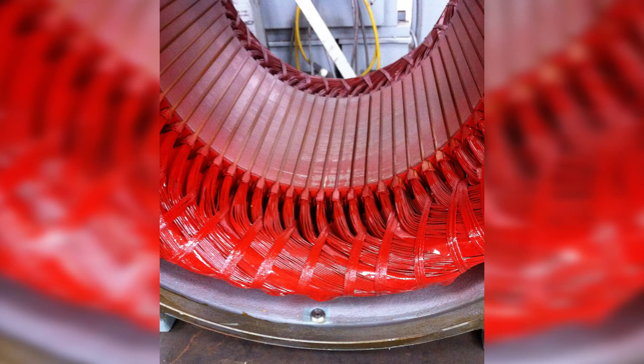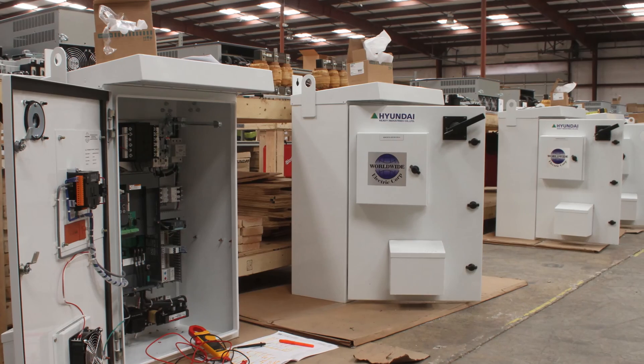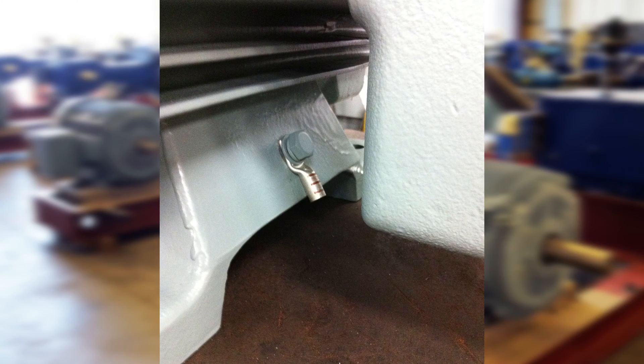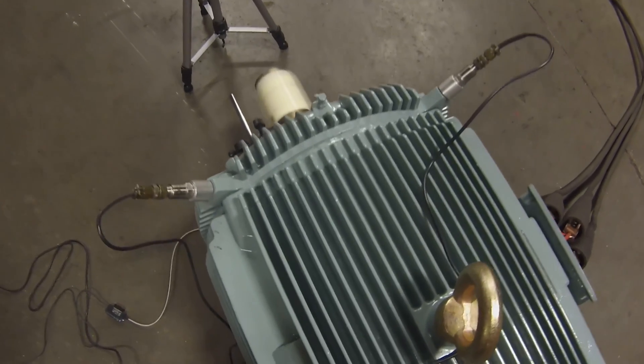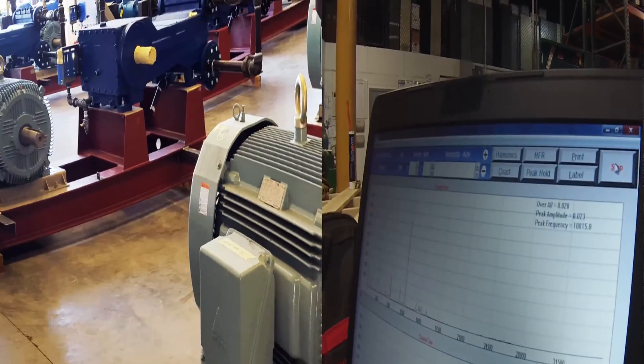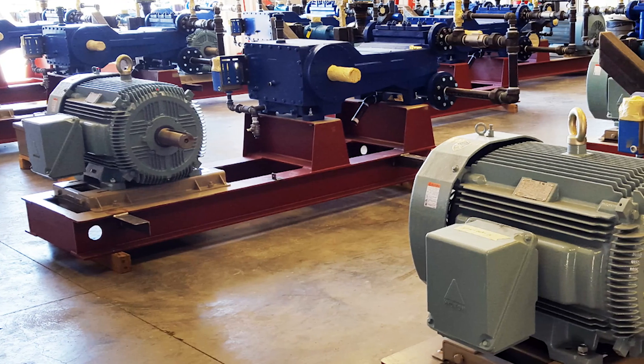Spike-resistant wire per NEMA MG1 Part 31, giving the inverter duty rating of 10-to-1 constant torque and 1000-to-1 variable torque. Foot flatness is .005 inches, along with the precision balancing, allows Hyundai to build a motor that exceeds the standard 841 vibration requirements. Typical vibration on these Hyundai motors is .04 inches per second peak-to-peak. These lower vibration levels help increase bearing life, giving you the reliability you demand.